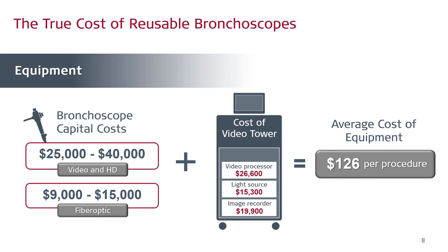And then to get to the average cost per procedure of $126, we took the purchase price and spread that cost across the lifetime of the scope or the tower, which we've estimated to be about 5 years. And then you also have to take into account the procedure volume in that facility. That's a really key factor here. We've used published data to estimate what a typical procedure volume for one bronchoscope looks like over the course of a year, and use that to get to this $126 per procedure.